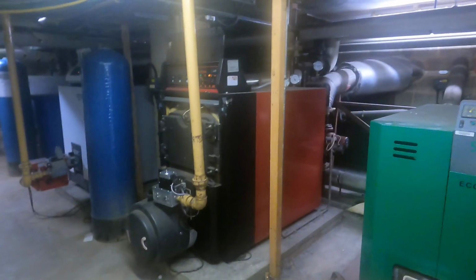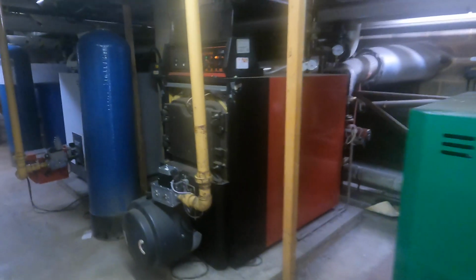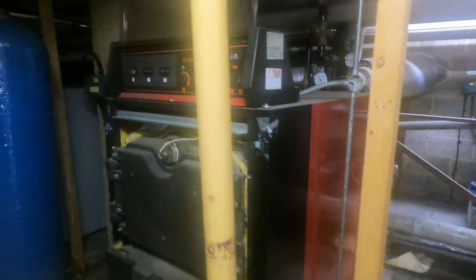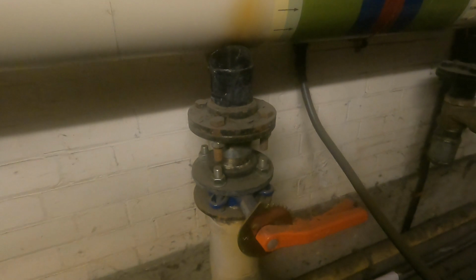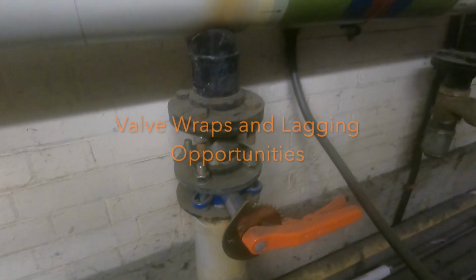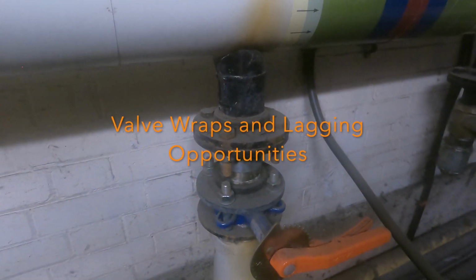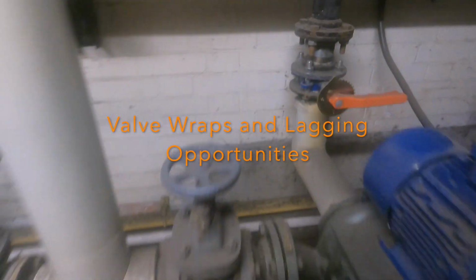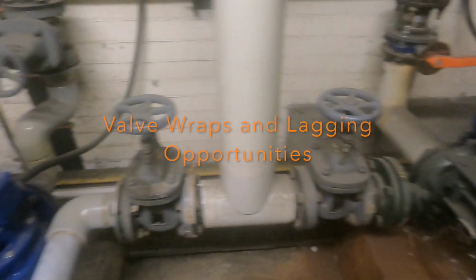Our last observation within here is the lagging, and you can see there's loads of areas for lagging opportunities to be replaced. We've got valve wraps that could be put in there to be extended, plenty of valves that haven't been lagged, and we've got areas where we've got no lagging at all.